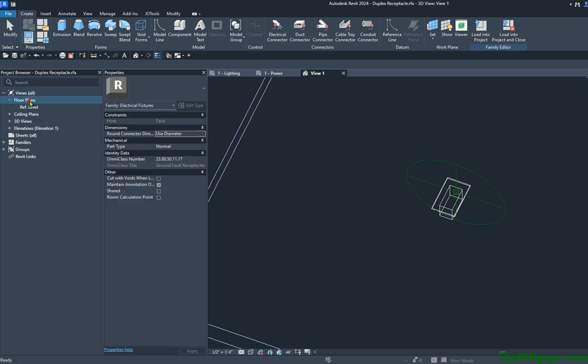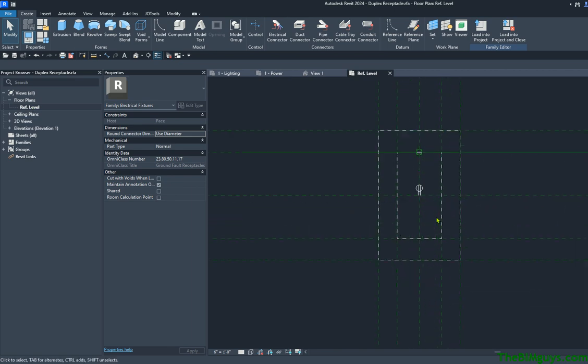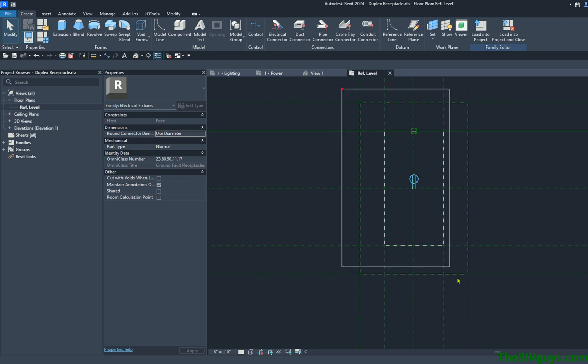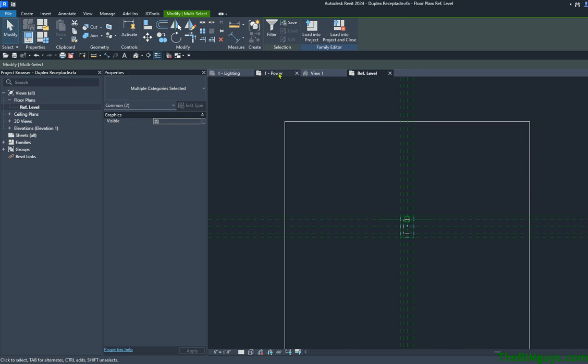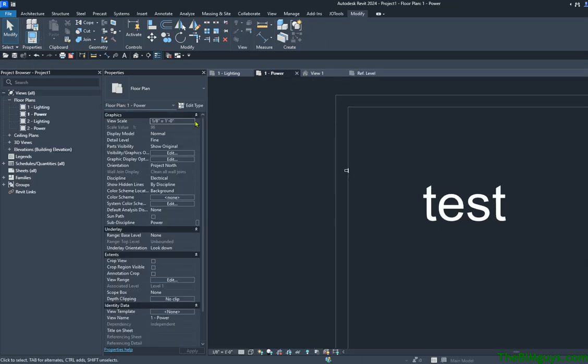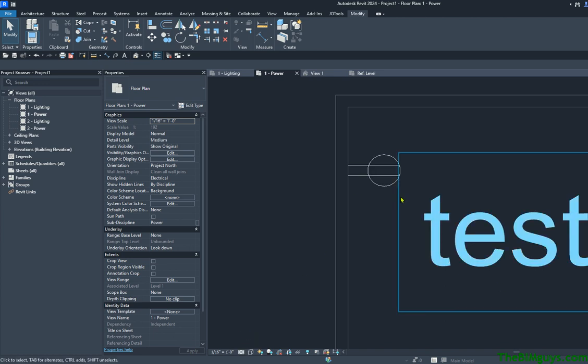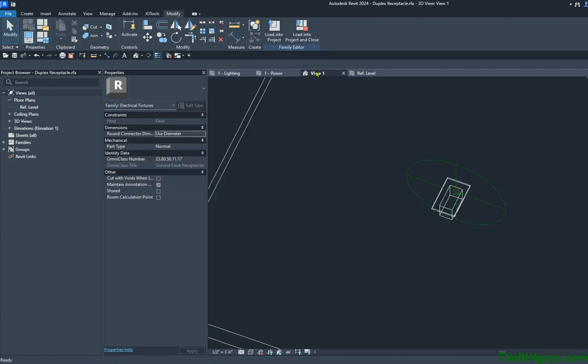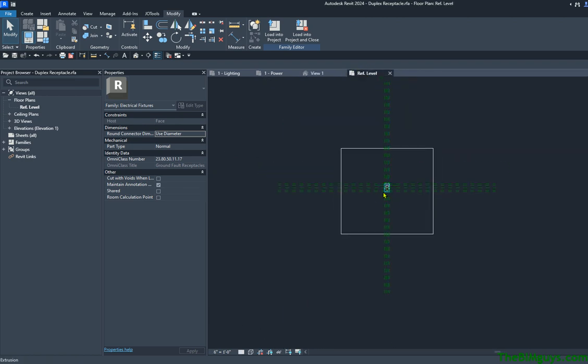I'm going to roll out the views and go to my Floor Plan view. When I zoom in really close, you're going to notice we have the physical box right here, and that physical box does not change. If we go back to the lighting plan or power plan and change the scale to a quarter inch or 16th, notice how the text got bigger but the physical box didn't, because it's a physical box. If I change back to annotative, like Medium, you'll see the annotative symbol got larger. So we're working with two families inside of here. Family number one is a physical box, and when I go to Reference Level, you can see the reference planes that drive the size of that box.